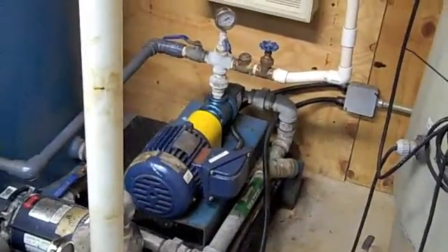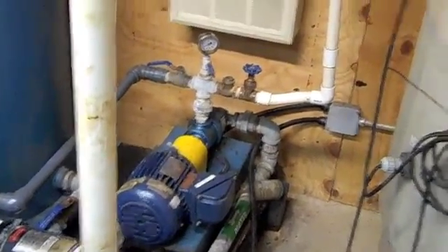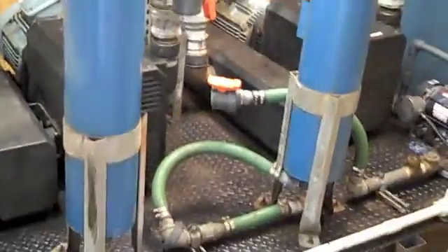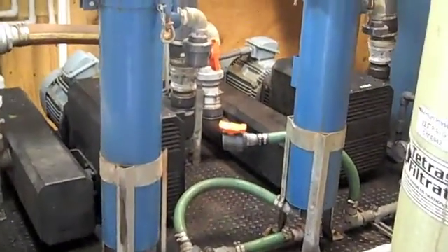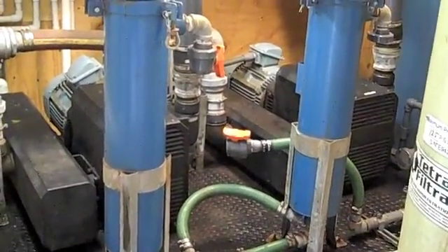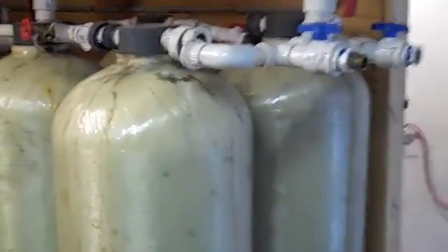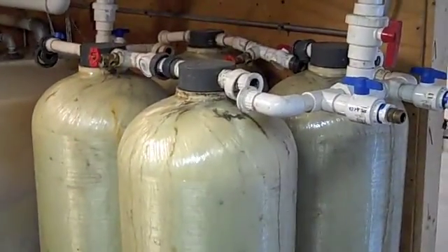The holding tank is equipped with float switches. Upon filling of the tank, the float switches turn on a transfer pump. The transfer pump engages and pumps water from the holding tank through 2 bag filter vessels in parallel. The water is pre-treated with bag filtration, 2 filters in parallel, before running through liquid carbon treatment.